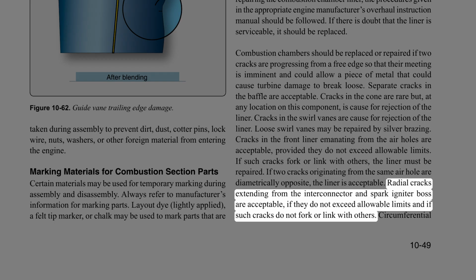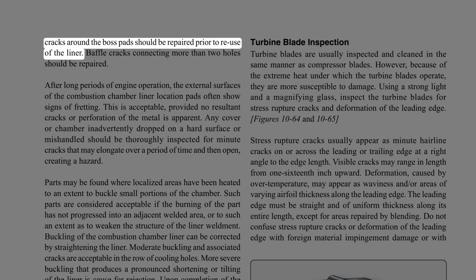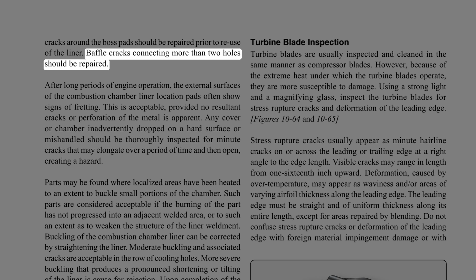Radial cracks extending from the interconnector and spark igniter boss are acceptable if they do not exceed allowable limits and if such cracks do not fork or link with others. Circumferential cracks around the boss pads should be repaired prior to reuse of the liner. Baffle cracks connecting more than two holes should be repaired.